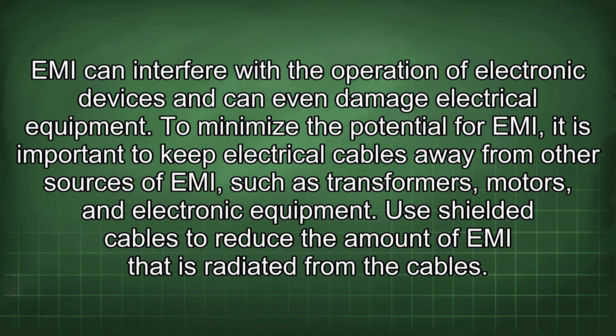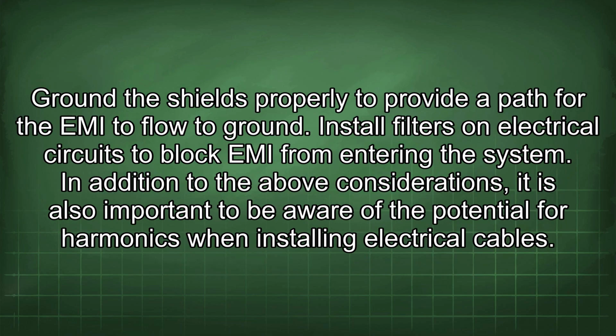EMI can interfere with the operation of electronic devices and can even damage electrical equipment. To minimize the potential for EMI, it is important to keep electrical cables away from other sources of EMI, such as transformers, motors, and electronic equipment. Use shielded cables to reduce the amount of EMI that is radiated from the cables. Ground the shields properly to provide a path for the EMI to flow to ground. Install filters on electrical circuits to block EMI from entering the system.